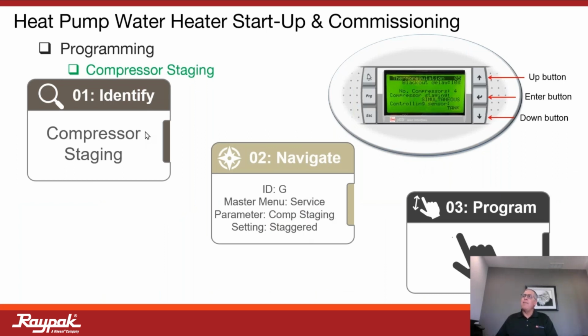So again, we can go back to navigating that menu for compressor staging, the number of compressors, as well as we can navigate to the simultaneous. We can hit the enter button and hit the up so that we can toggle on staggered instead of simultaneous. I think for domestic water production, I would leave it in the simultaneous. Perhaps for space heating in multiple units, maybe there's a little bit more elegance or a conversation that we can have about using the staggered approach. I think you'll develop it over time, but I think for domestic water production, simultaneous is sufficient because we want to satisfy that load as quickly as possible. With space heating, we're not turning on a dime trying to satisfy set point. We can stagger those on based on differential.